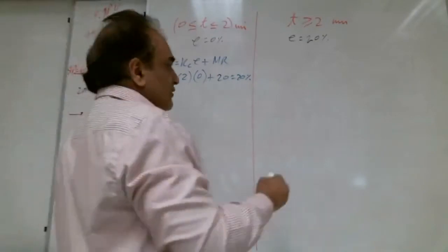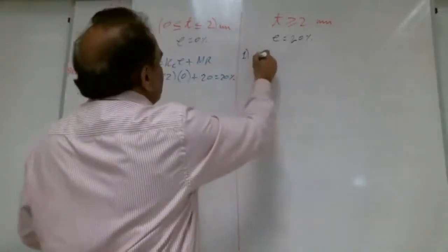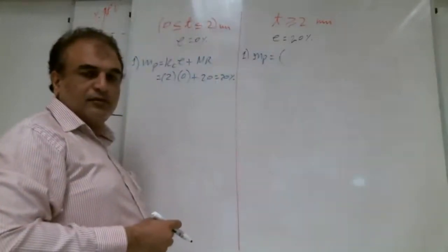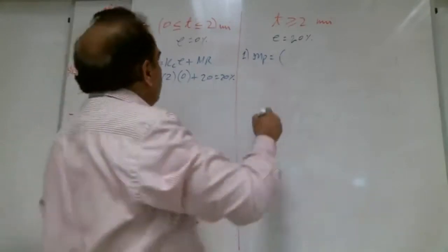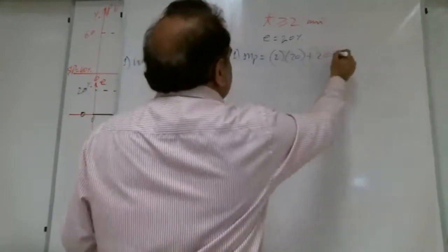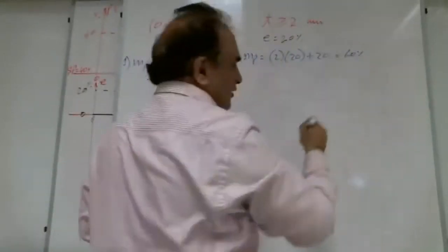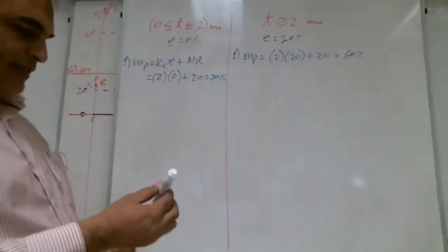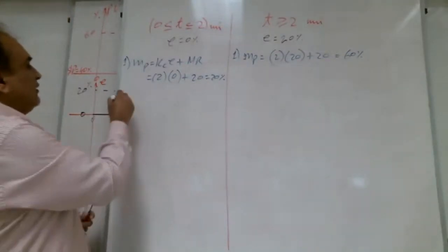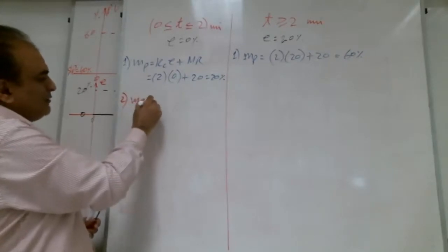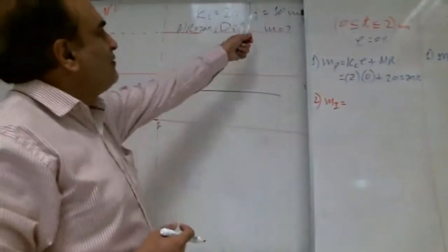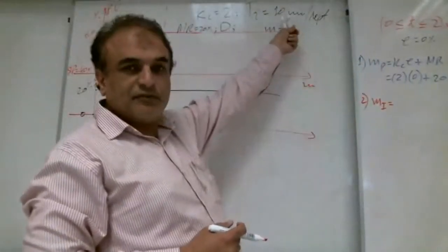That's good. Okay, what is the first step here? MP is equal to how much, Kc, Shabab? Multiply 2 by 20, plus 20, 60%. Very good. Lot of brothers are writing 60%. Very good, Shabab. Second step always is MI. This is integral action. See, the integral time is there, 10 minutes per repeat.